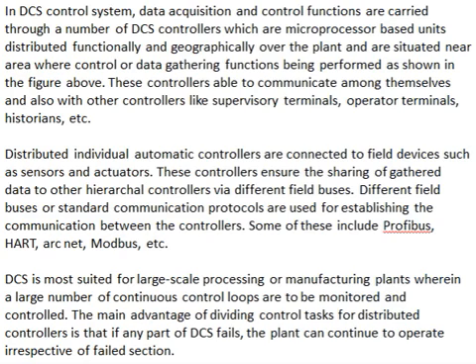In a DCS control system, data acquisition and control functions are carried out through a number of DCS controllers, which are microprocessor-based units distributed functionally and geographically over the plant and situated near the area where the data gathering functions are being performed, as shown in the figure above. These controllers are able to communicate among themselves and also with other controllers like supervisory terminals, operator terminals, historians, etc. Distributed individual automatic controllers are connected to field devices such as sensors and actuators. These controllers ensure the sharing of gathered data to other hierarchical controllers via different field buses.